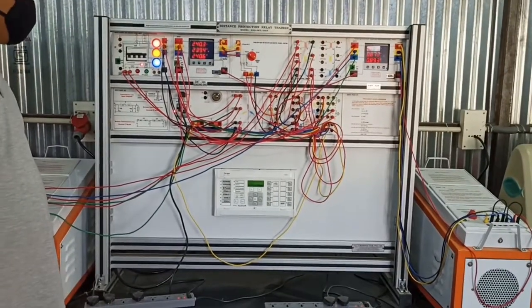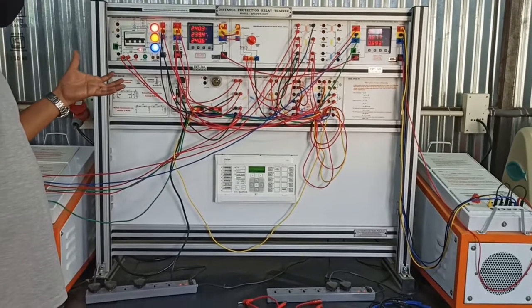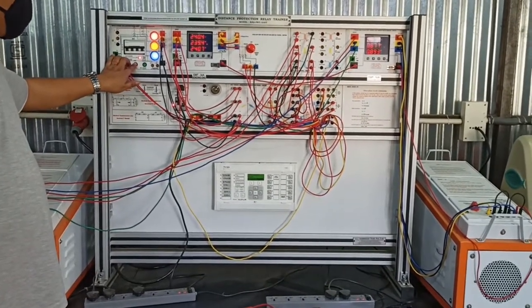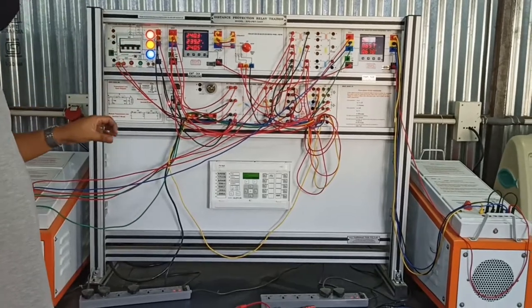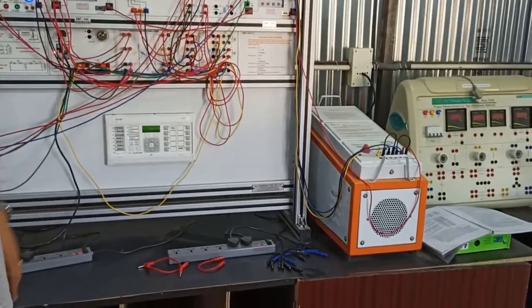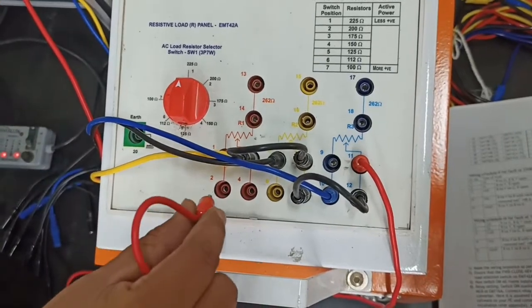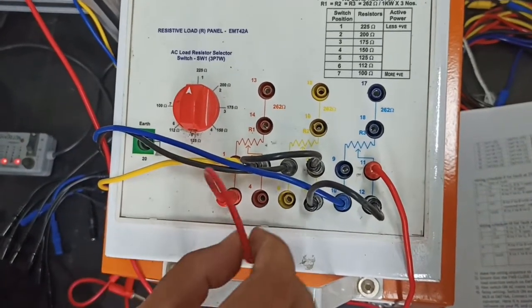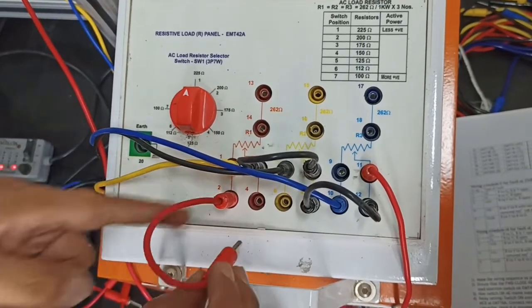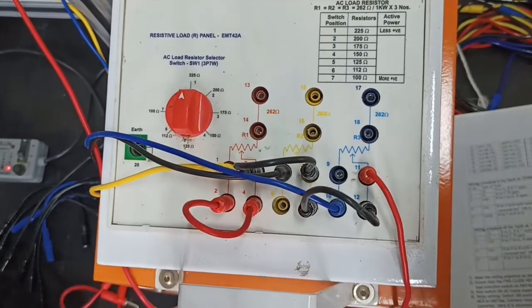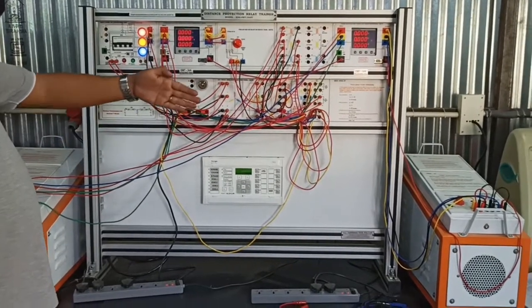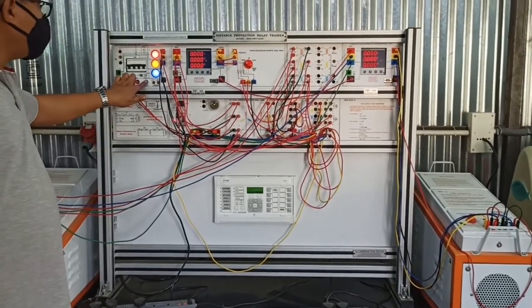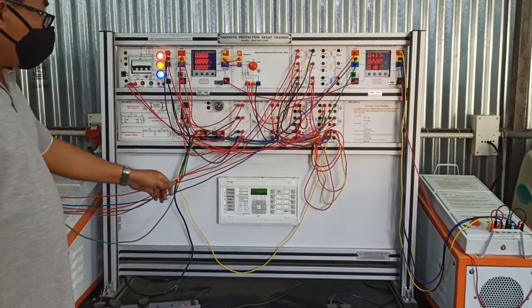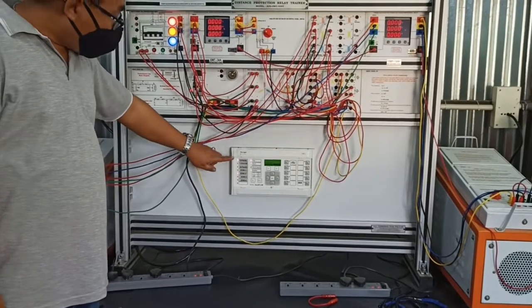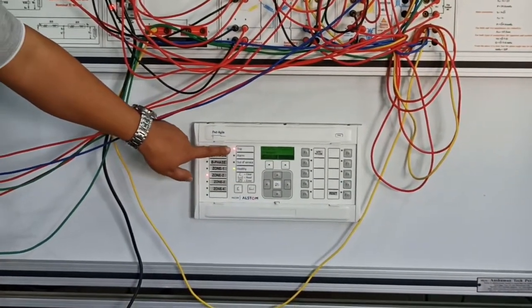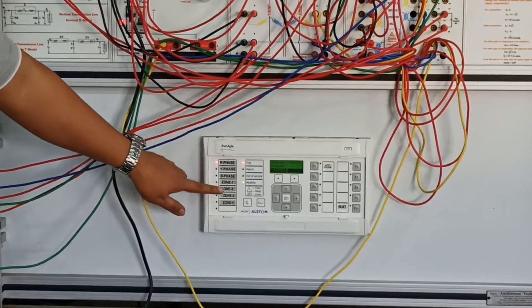In order to make the line to ground fault, we have to stop the three-phase supply and then make the connection here. For a single line to ground fault, we connect 2 and 4. Now we have made the line to ground fault on the load side. Now we will start it, and from here we can see that the phase is tripped and the fault is in zone 2.